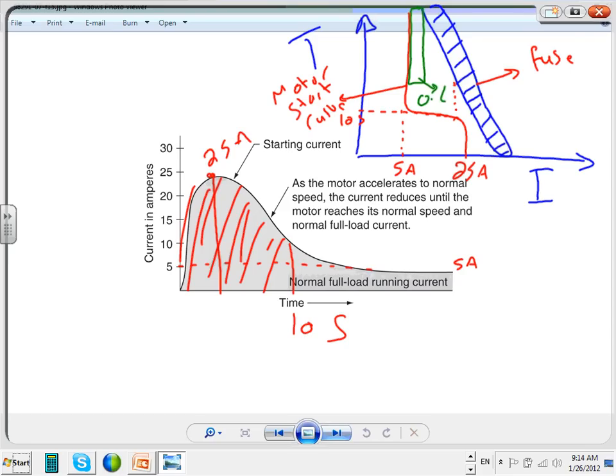I want you to remember this one, guys. We're going to be doing it because they call it overcurrent protection coordination. And we're going to be doing it with a software. This is bring it home, where the fuse is protecting from short circuit, the overload protecting you. Can you see how the overload is right next to the 5 amps? So if it exceeds more than 5 amps slightly, it trips. So just remember that.